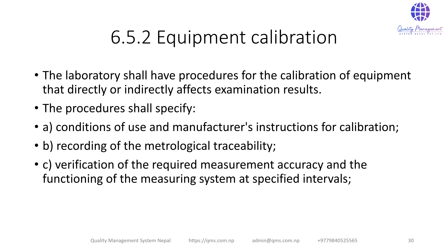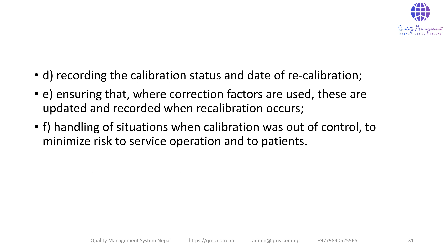6.5.2 Equipment Calibration: The laboratory shall have a procedure for the calibration of equipment that directly or indirectly affects examination results. The procedure shall specify: conditions of use and manufacturer instructions for calibration; recording of metrological traceability; verification of the required measurement accuracy and functioning of the measurement system at specified intervals; recording of calibration status and date of recalibration; ensuring correction factors are updated and recorded when recalibration occurs; and review of handling of situations where calibration was out of control to minimize risk to service operation and to patients.